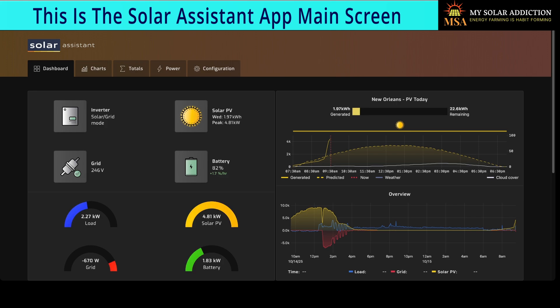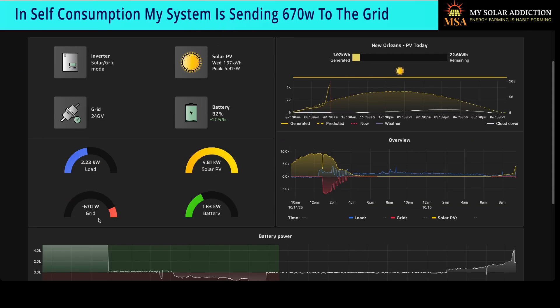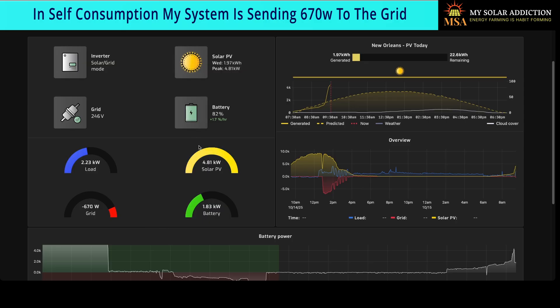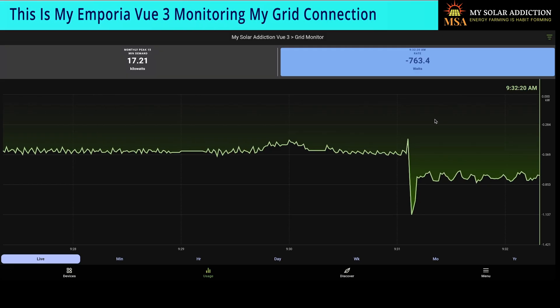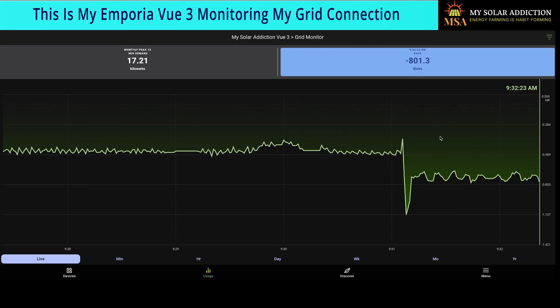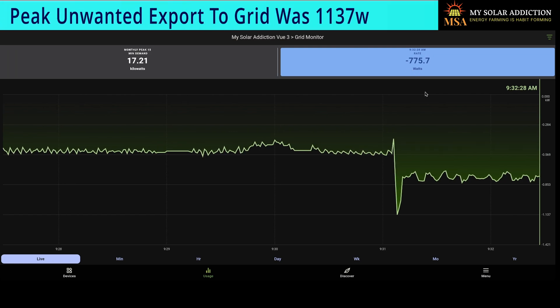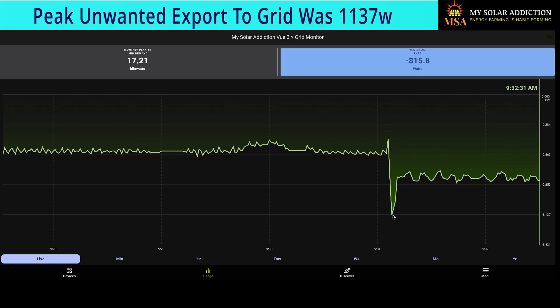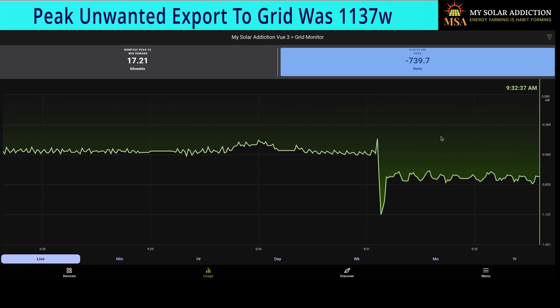So this is what grid trickle looks like. I disabled off-grid mode so I could show you guys what grid trickle is. You can see right now, even though I'm set to self-consumption and I have space available in my batteries — we're at 82% — 670 Watts is going to the grid right now. To verify that, I go to Emporia Vue. I have a grid monitor with CTs on my grid connection. As you can see, it's fluctuating all the way up to 800 Watts going to the grid, and it peaked out at 1137 Watts. That's a lot of juice — it's not some small amount.